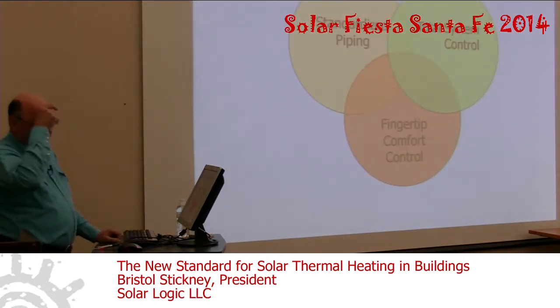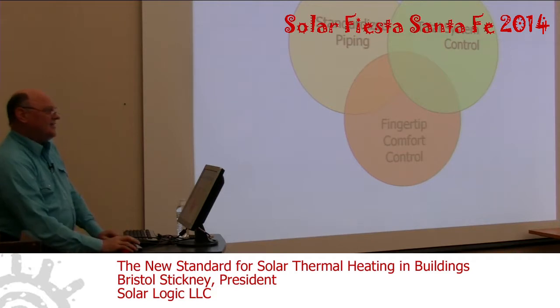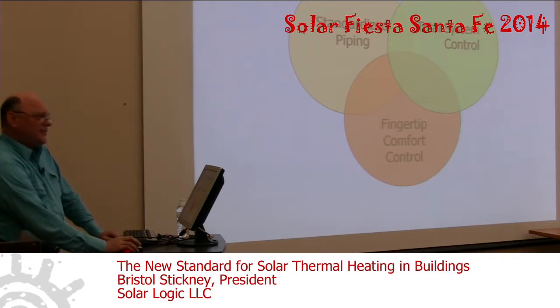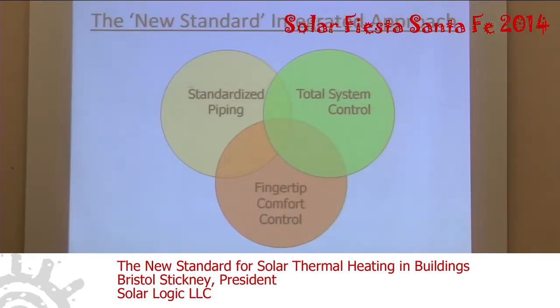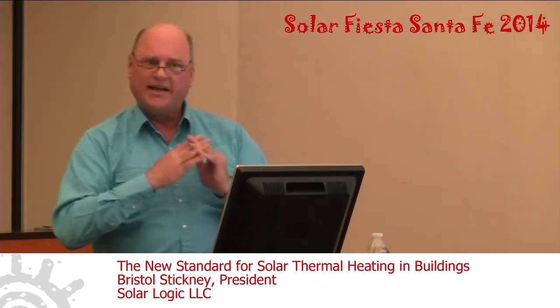So how do we do it? What is the new standard? The new standard is you design the whole system as if it was one package. You design a standardized piping system, and I'll show you how that's done in a minute. And while you're designing the plumbing for the heating system, the piping, you're also simultaneously designing the control system. So the controls and the plumbing and all the plumbing components go together. They were designed to work together.